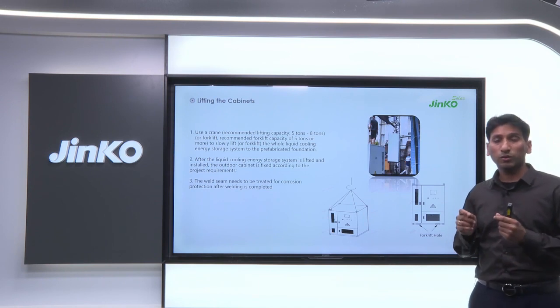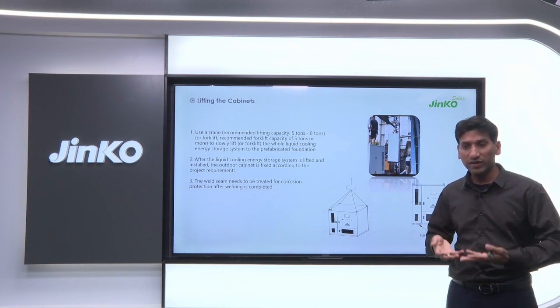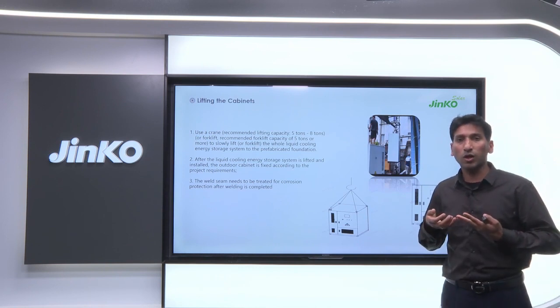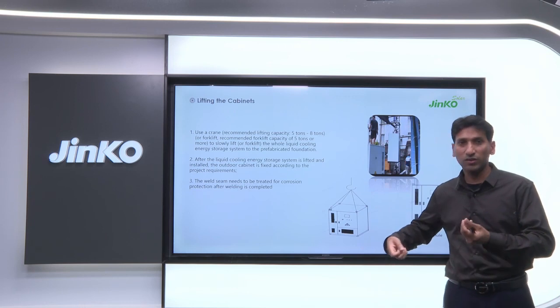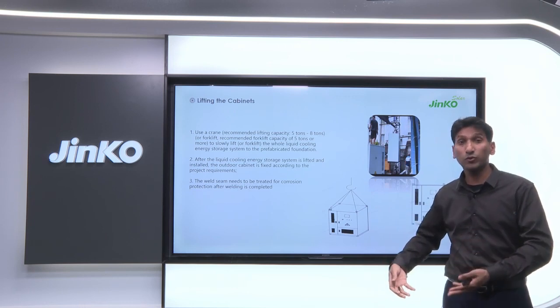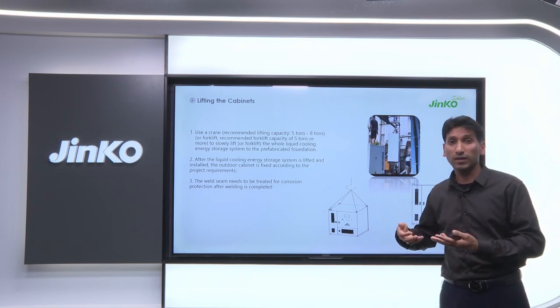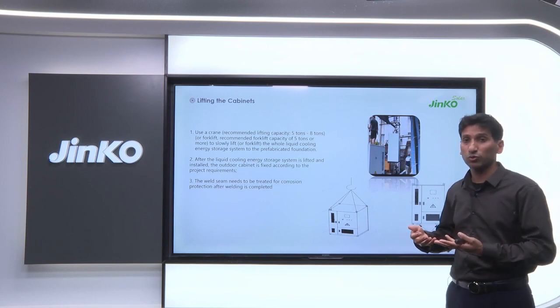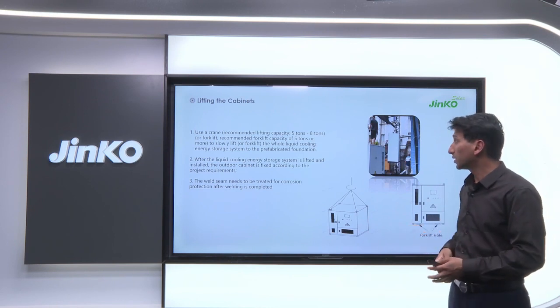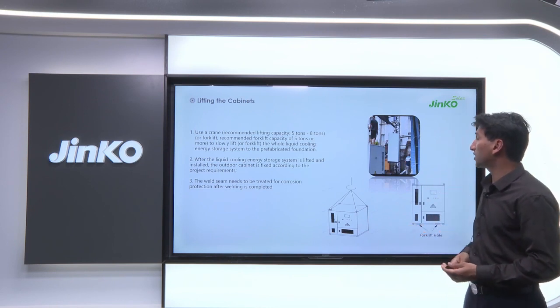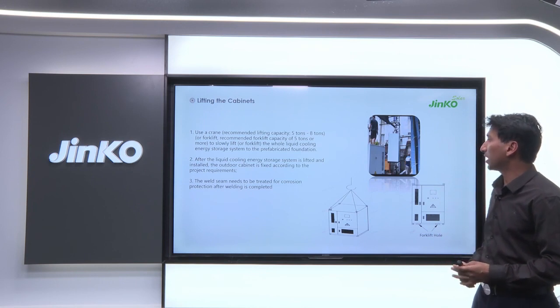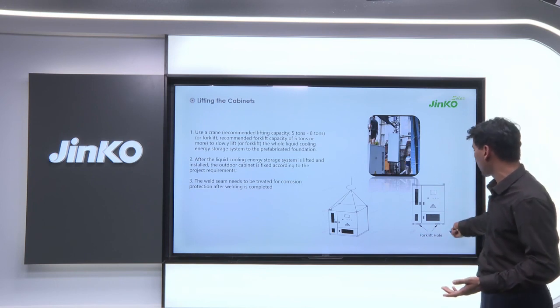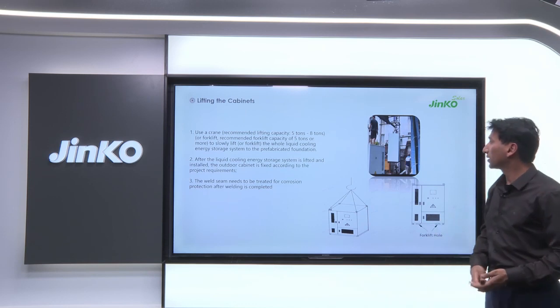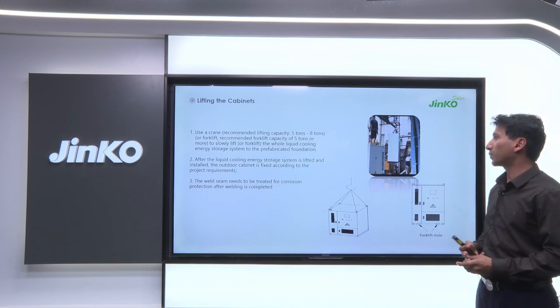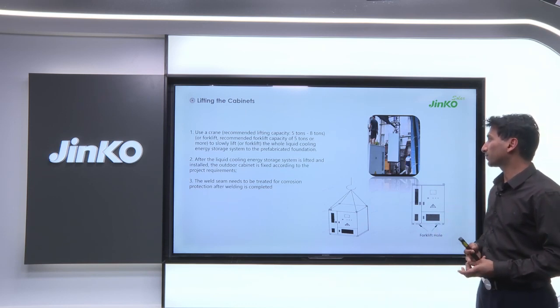lift one cabinet. It's not allowed to try to lift two cabinets together to save time. That may cause damage to the equipment and maybe to the personnel working on the site. So the lifting capacity is 5 tons to 8 tons. If you're using a forklift to carry them from here, a capacity of at least 5 tons is sufficient.